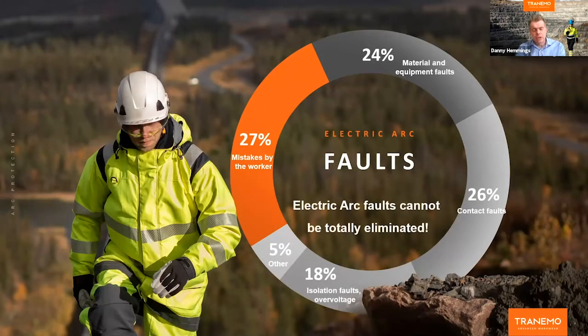Obviously, from our perspective, we focus on the holistic protection of the worker from a clothing and PPE point of view. And I think the biggest thing for everyone to really understand is we can never be at a point where arc flash is eliminated, because at its core, the issue with an arc flash is it's not a preordained event. So as we see there, in a percentage breakdown of arc flash incidents, over a quarter are mistakes by the worker, a quarter material and equipment faults, a quarter a contact fault. So these are all things that really don't necessarily present themselves until the actual event happens. So with elimination being at the forefront of the PPE pyramid, the problem with arc flash is that you can never really eliminate the potential risk for an arc flash. So mitigation is so important.